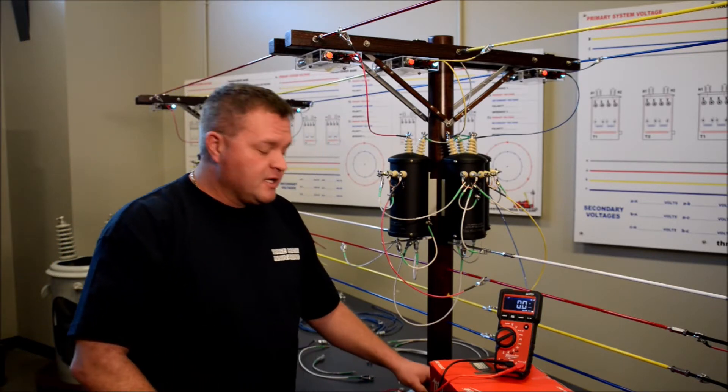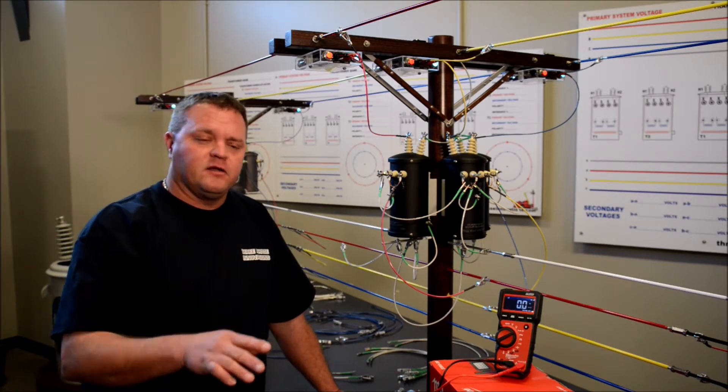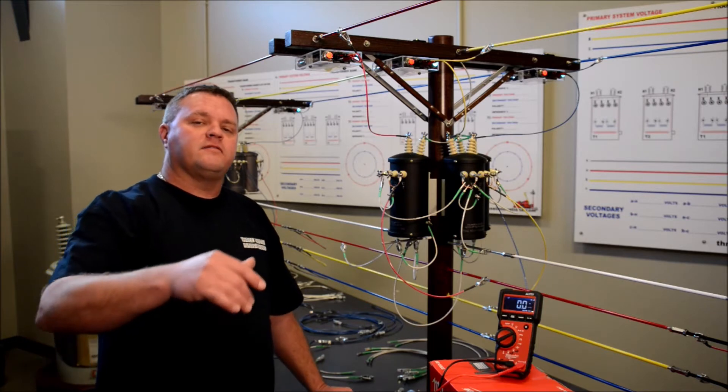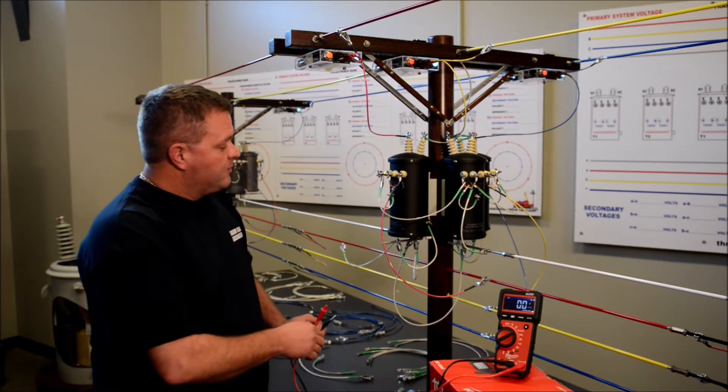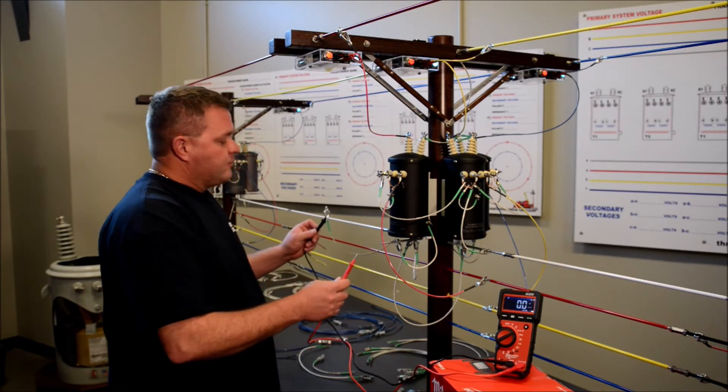And something else I want to show you - why I've got this back here floated. If for some reason the wye on the high side was to become loose for any reason, hang down on the pole or whatever, you're working out of a bucket, just be aware of that wye. If the floating jumper that was tied, well it's now floating, it comes loose.